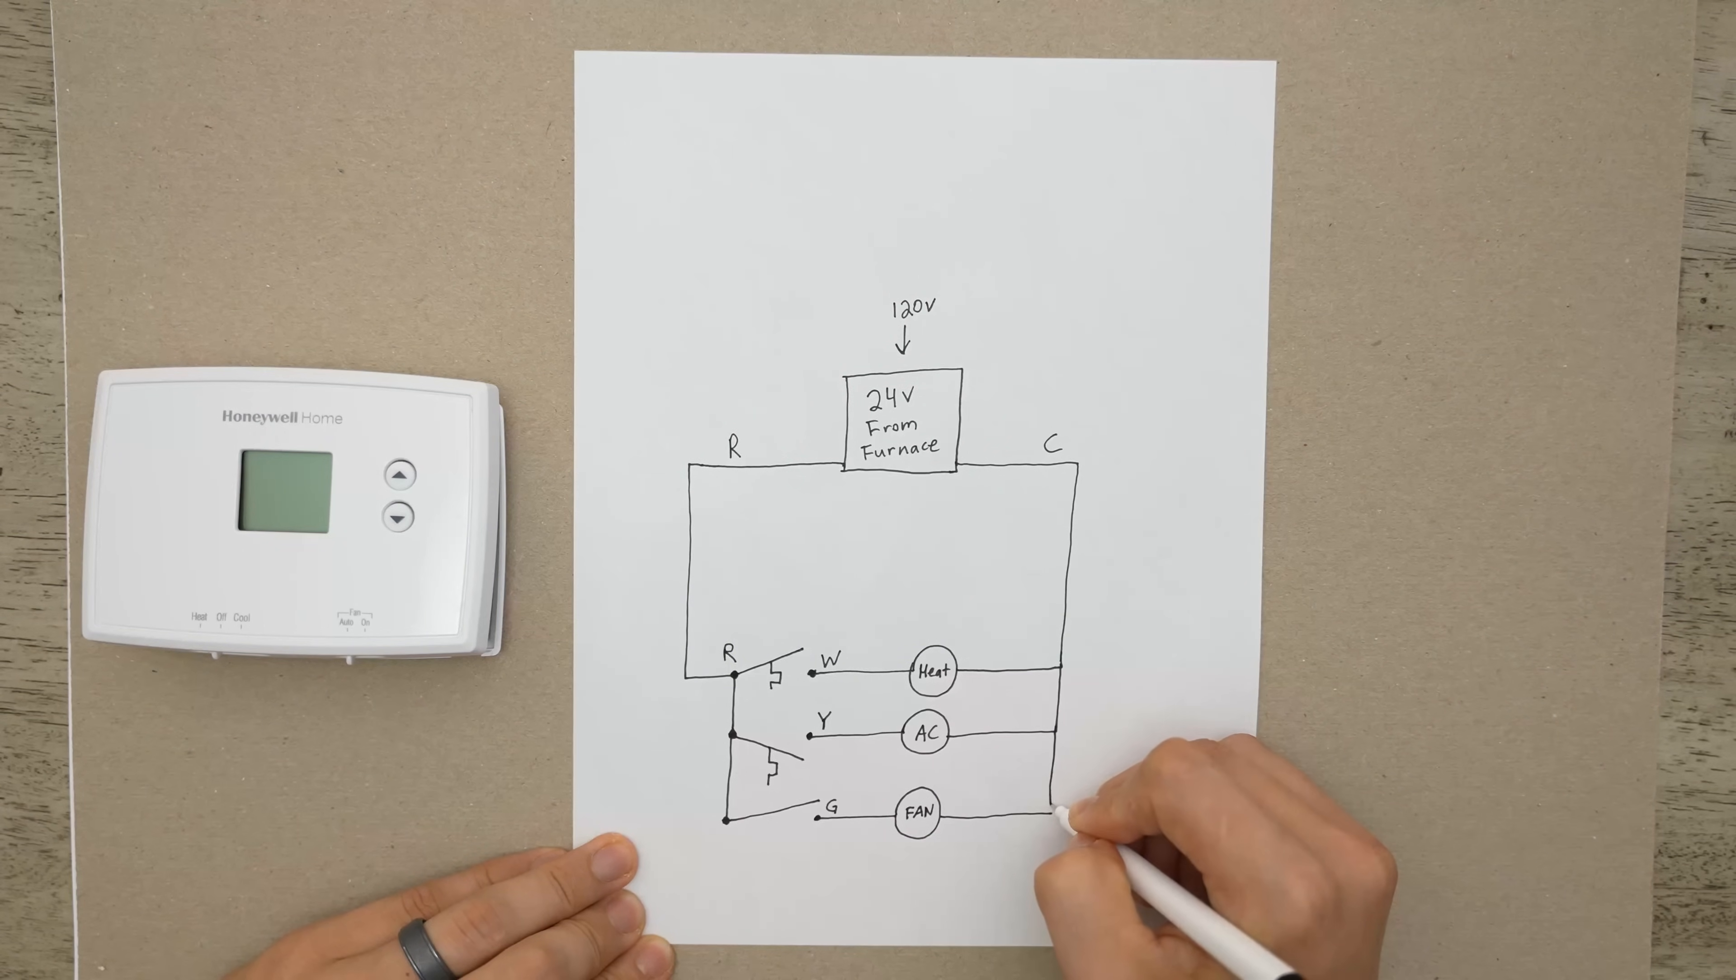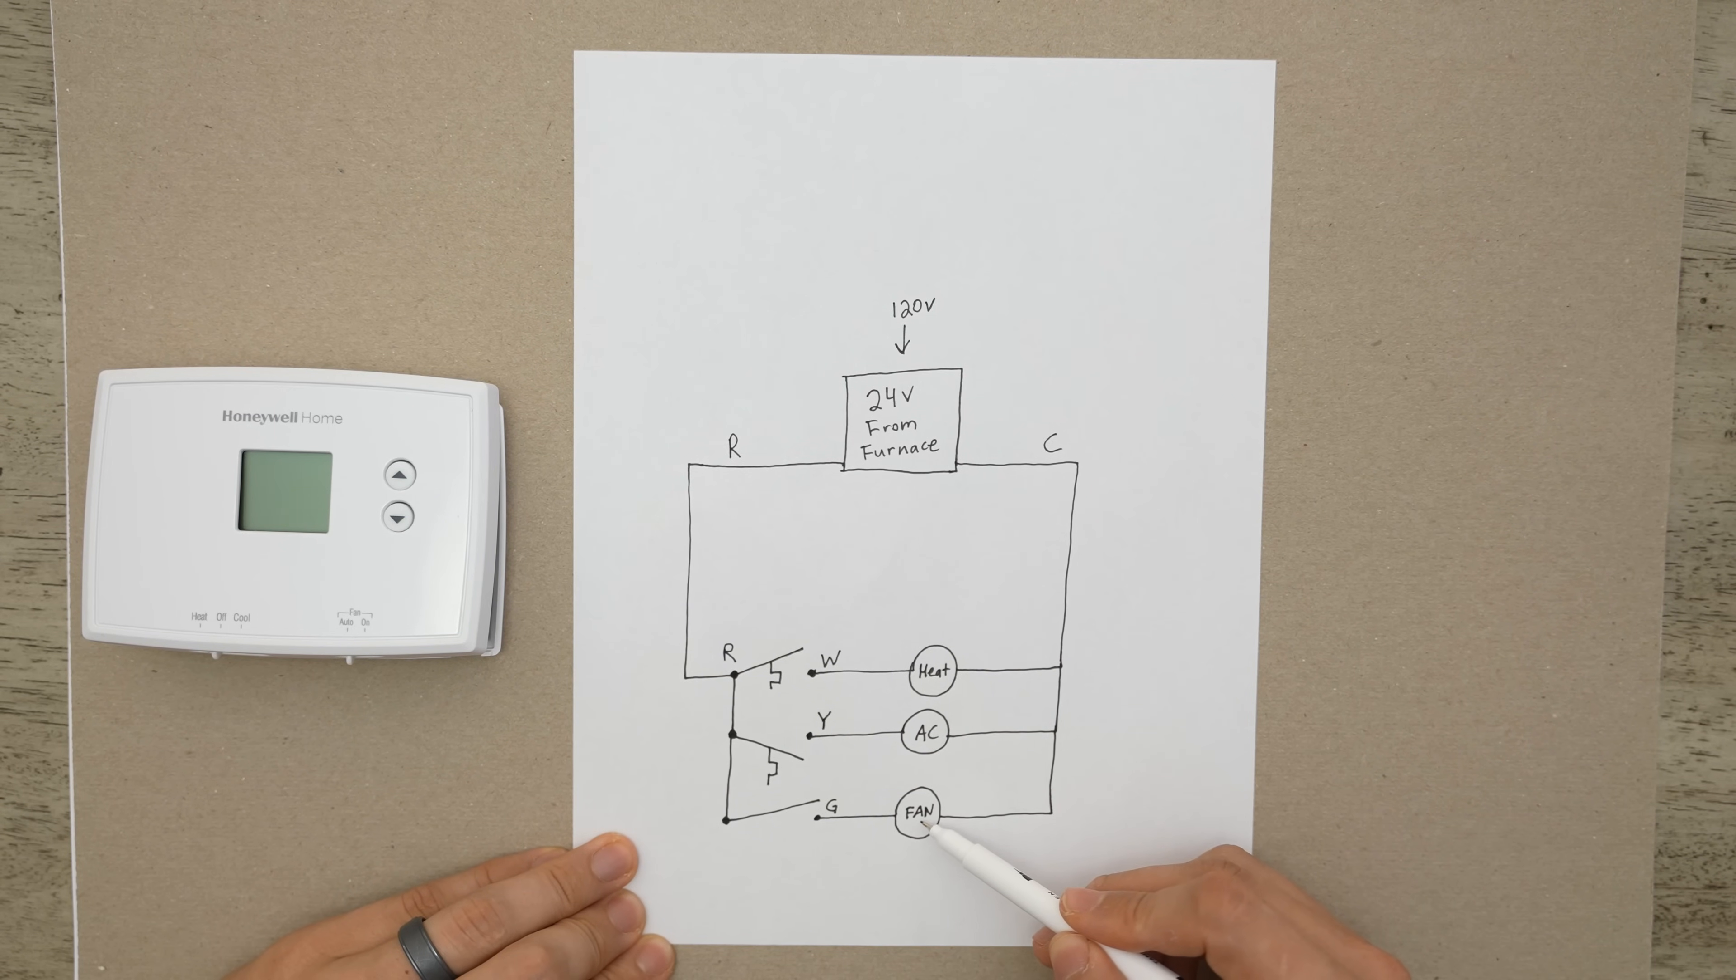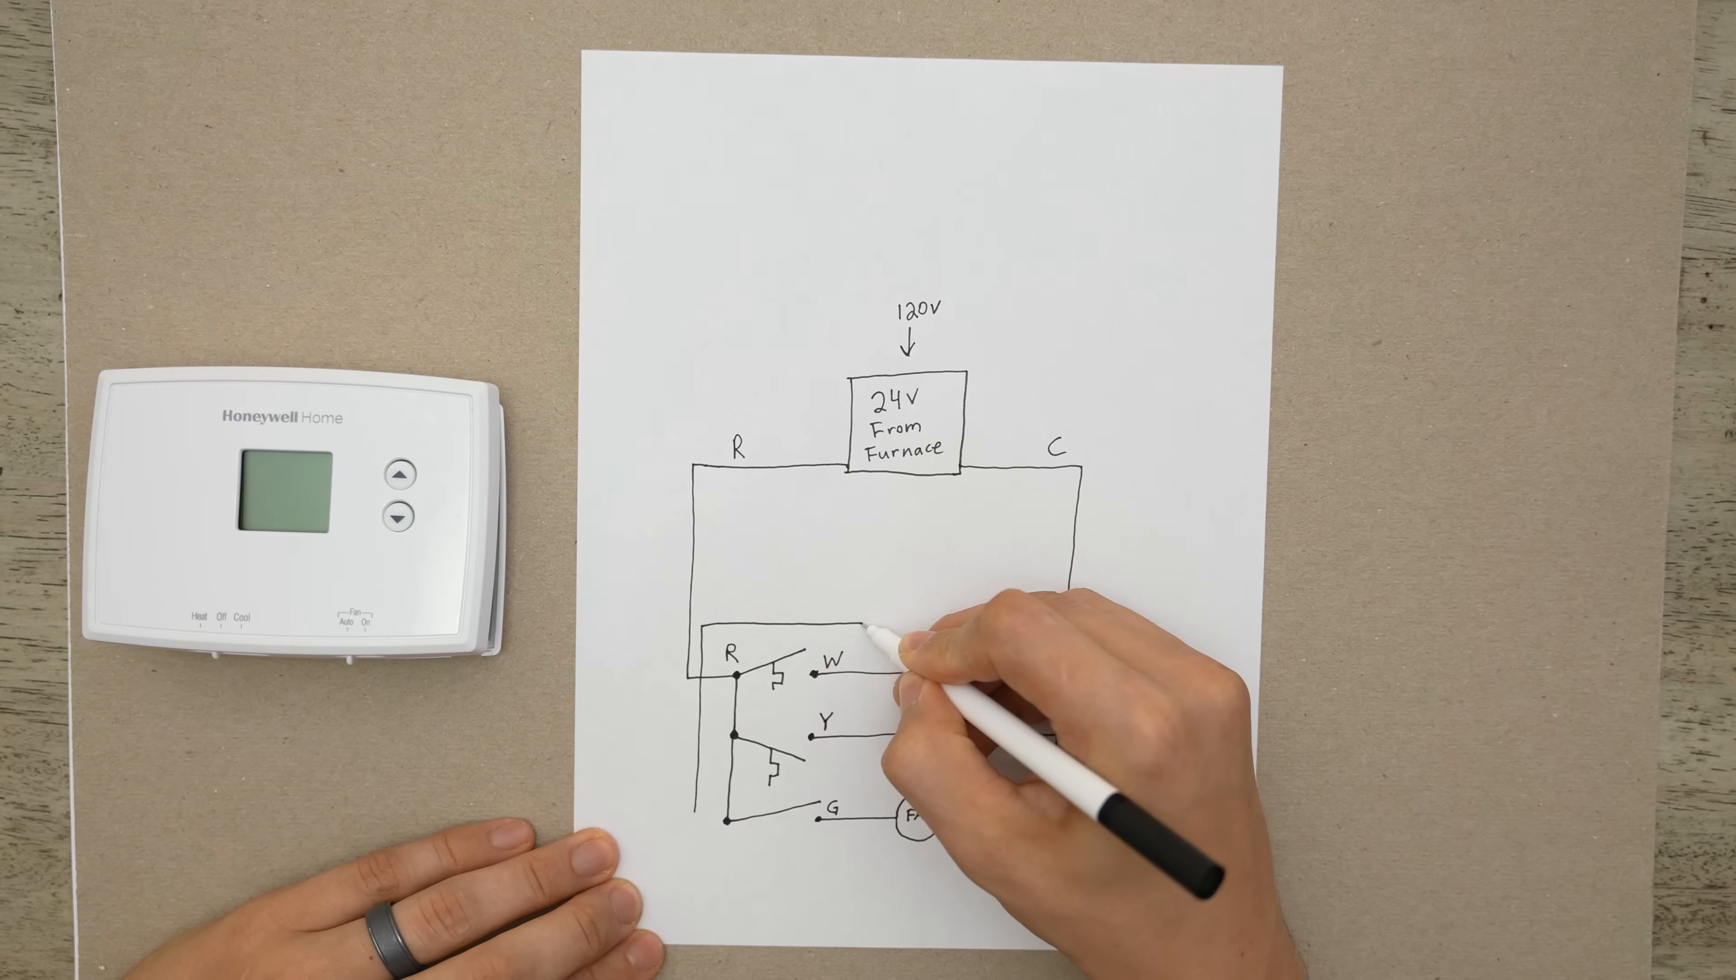And whenever G closes, our indoor blower fan comes on inside of the furnace. And even though I write heat, AC, and fan, it's actually more like the gas valve coils, the contactor coil inside of an air conditioner outside, and it would be a fan relay coil for this one. But for simplicity's sake, I'm just going to write heat, AC, and fan. In this little diagram, the thermostat part would be this part right over here.